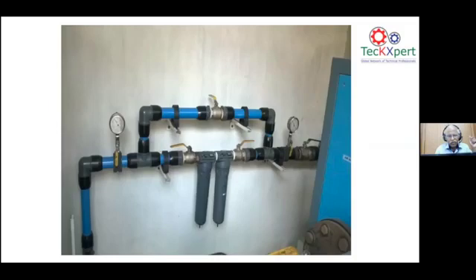Across the dryers or across the filters, whatever is there, the coalescent filters or the water separation filters, it is showing this red and green gauge. It is not a correct indication, as we have come to understand from the field. Instead of that, let us have two gauges on the incoming side and outgoing side. We can definitely monitor the pressures to know the pressure differential across the filter, how much is allowed, what is the minimum, and what is the maximum that is to be kept.